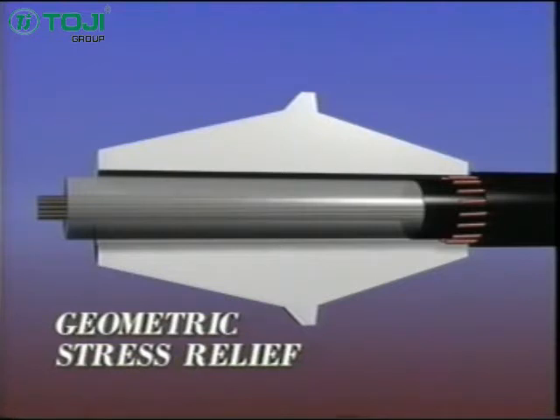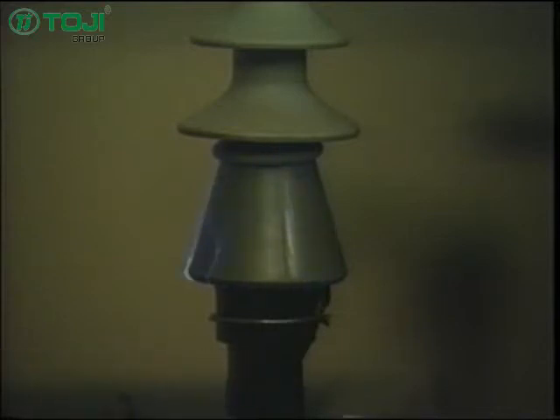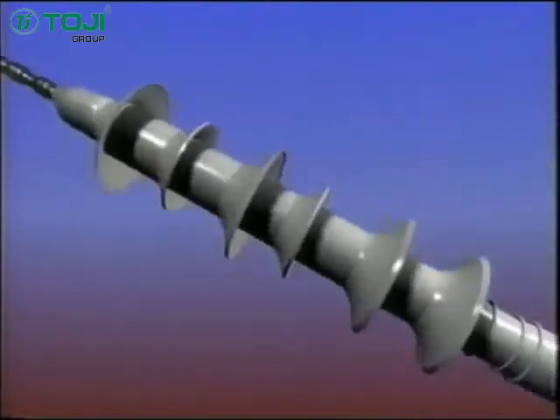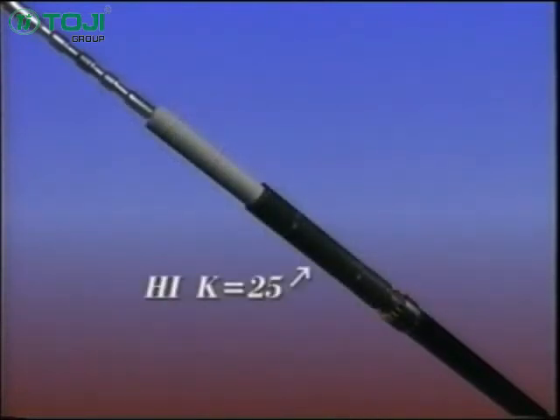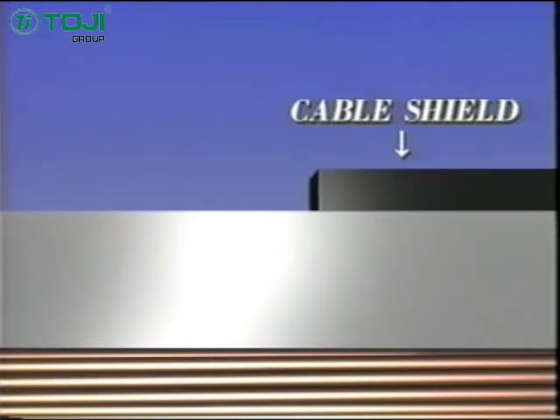One is the geometric method. This is accomplished by building the insulation material up and continuing the shield to the exact focal point of the electrical flux. The geometric stress cone method is old technology and requires a more bulky, less efficient configuration. The 3M solution utilizes a highly effective material with a very high dielectric constant K for dealing with electrical stress. Our high K material has a dielectric constant 10 times higher than that of most cable insulation. Stress relief is accomplished by covering the end of the cable shield with a layer of the high K material.